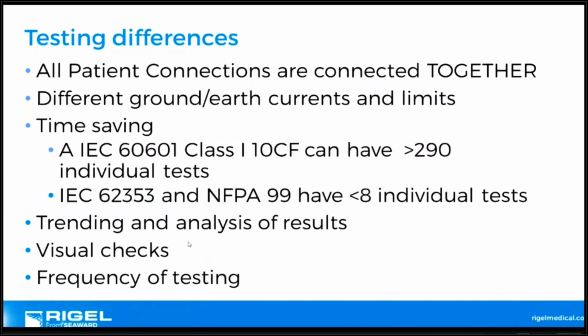62353 pretty much stresses the trending and analysis side. Both NFPA 99 and 62353 stress visual checks. 60601 doesn't. And then the frequency of testing: 62353 typically annually, but again, this would be how risk averse you want to be within your organization, and if you want to follow medical equipment manufacturers' guidance.